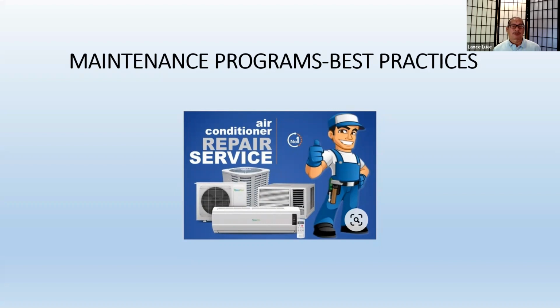If you don't have one, because some manuals get lost, or the air conditioning system is 20 years old and the manual fell apart and got thrown away, all you do is find out the brand and contact the manufacturer to get the manual. You read the manual, because it's the Bible for maintenance. It'll say your filter has to be changed and inspected every 6 months, your motor has to be inspected and lubricated, components every year, whatever it says. That dictates the schedule, so you don't have to guess when to call the air conditioning mechanic - it's right there.